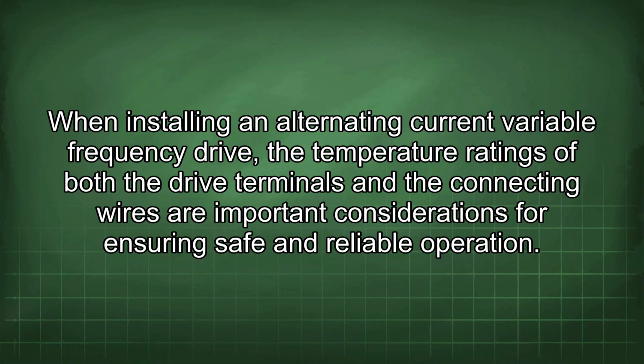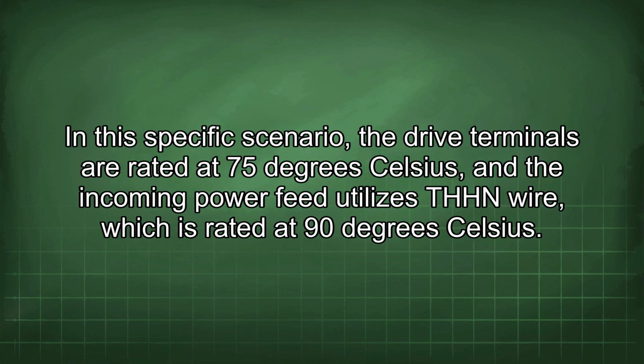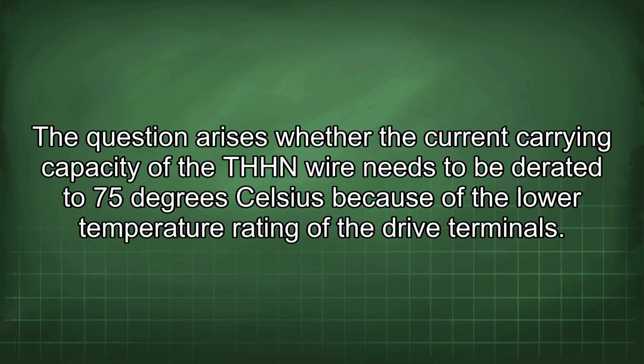When installing an alternating current variable frequency drive, the temperature ratings of both the drive terminals and the connecting wires are important considerations for ensuring safe and reliable operation. In this specific scenario, the drive terminals are rated at 75 degrees Celsius, and the incoming power feed utilizes THHN wire, which is rated at 90 degrees Celsius. The question arises whether the current carrying capacity of the THHN wire needs to be derated to 75 degrees Celsius because of the lower temperature rating of the drive terminals.